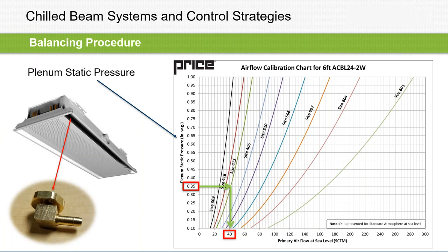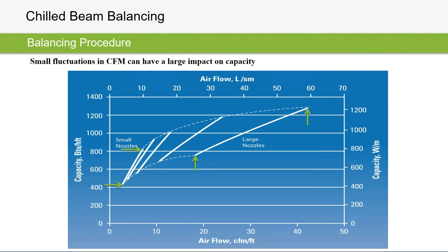So it is like a one-step removed process. You're not going to directly measure the CFM. You do have to go look at that pressure and see what we've correlated that to on this chart. So a little bit different from a typical system. And we'll talk about some more pitfalls a little bit later on as well.